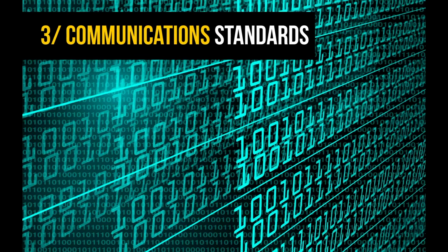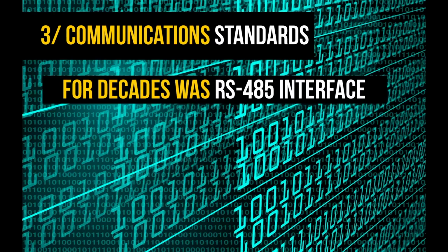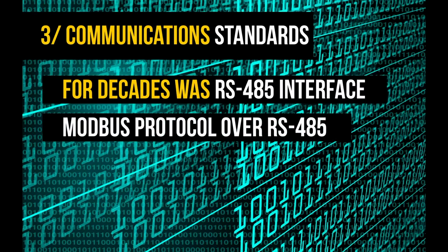Characteristic 3, communication standards. Given the mandate of visibility of information, communications to the meter is a key consideration. For decades, submeters, single point or multipoint, have relied on older communication methodologies to collect information. Typically, this has taken the form of an RS-485 interface leading back to a proprietary collector, using proprietary communication standards. So difficult to use, it often ends up that the facility manager just goes back to the manual reading of the meters, and ultimately the system will likely fall into disuse.